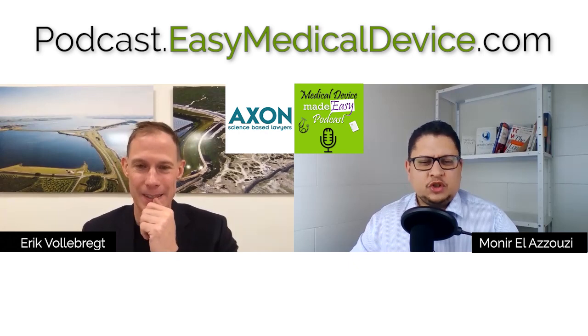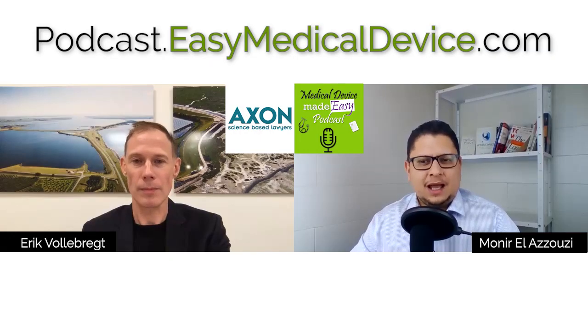Just for a story, I had some people from the US contact me who have a class 1 exempt device, and they want to put it on the market in Europe. They were saying to me, it's crazy how much it costs to be compliant with the European regulation when we are class 1, when in the US it doesn't cost so much. Now they are starting to really see that all the requirements cost money: creating a technical file, creating a compliant quality management system, finding an authorized representative, etc. There is a lot that has to be done, and a lot of companies were really surprised by how much it cost.